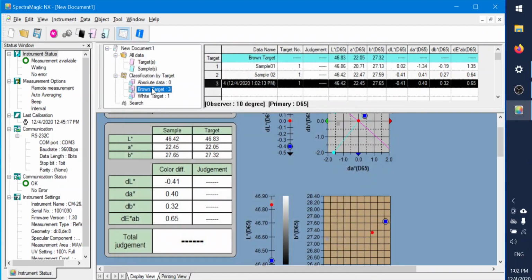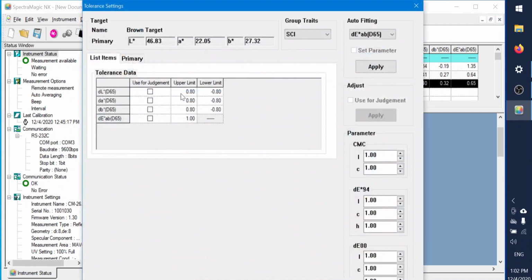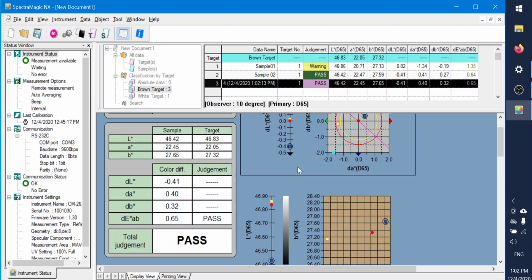However, in most scenarios, we do not set a default tolerance, we set an individual tolerance. So just for the brown target, I'll set it to 1.5. I'll click enter on my keyboard, it will save.